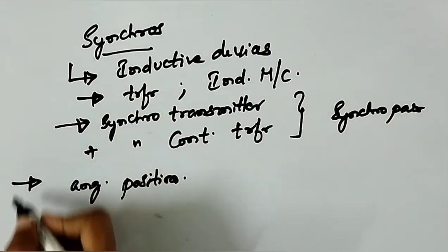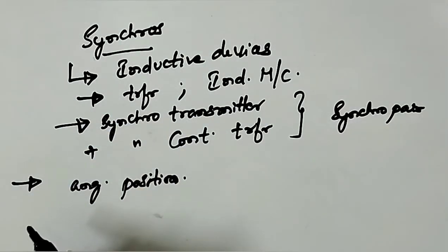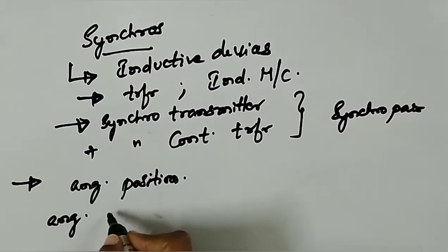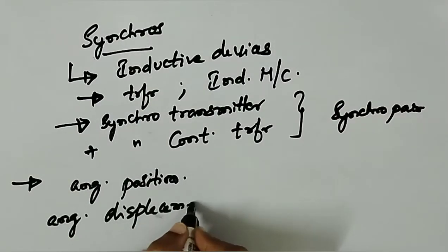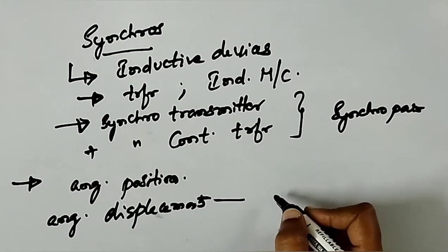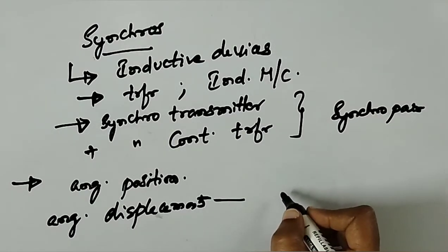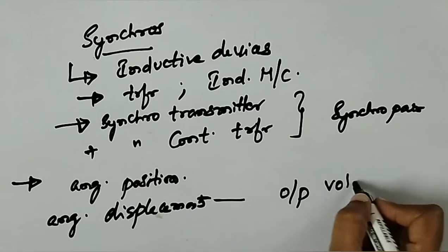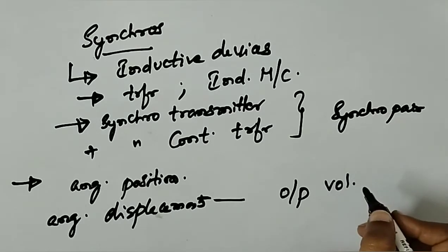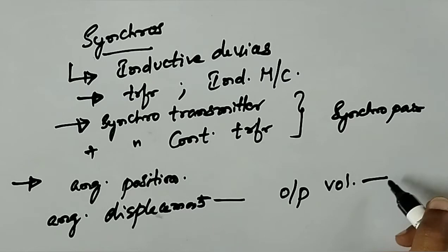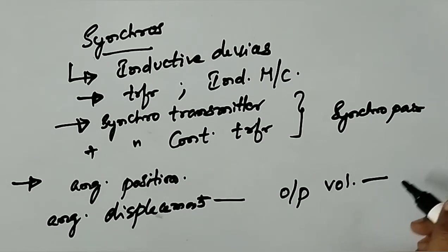This synchro pair would compare two angular displacements, and that particular difference is measured in terms of output voltage - that is, in a linear relationship with the angular difference of the axes of both shafts.